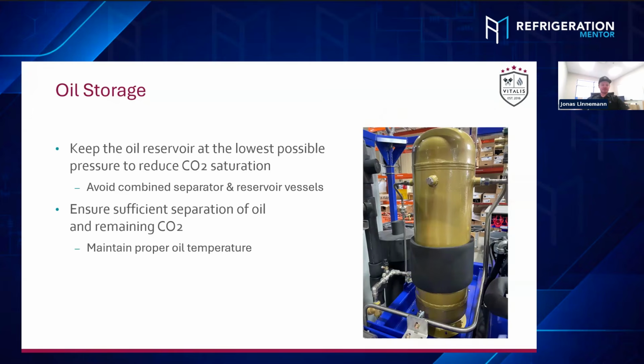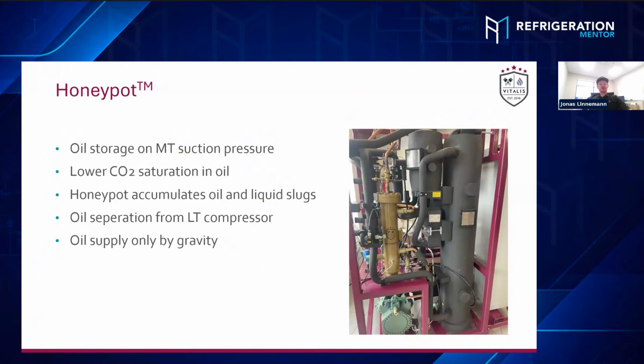So this is the normal oil storage, I would say, which is very common in the field. We also do a little different system, which we call honeypot. The honeypot basically is an accumulator. You can see up here, that's a very small, tiny unit, especially made for convenience stores, where we build basically a suction accumulator in the suction line of the medium temp compressor. But we also return the oil coming here from the oil separator through that little valve. We return that into that vessel as well.